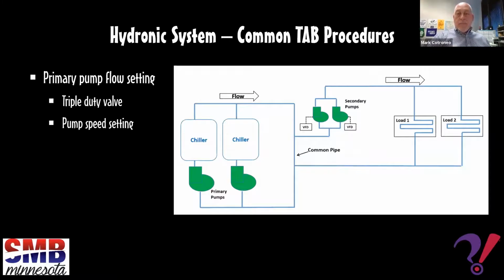For a constant volume primary pump, we would verify that all control valves are open first and foremost. Then we would verify that the gauges are installed in the correct location to gain a measurement, which is directly at the inlet and the outlet of the pump. If they are in the correct locations, the discharge valve will be slowly closed and the gauge read to establish the shutoff head. This process verifies the size of the installed impeller. Starting with the shutoff head that was measured, a new pump flow curve is drawn. Then the discharge valve is opened, the inlet and discharge gauges are read, and the difference in their values is plotted to intersect on the new pump curve. If the flow is too high, the triple duty valve or balancing valve is closed to create pressure and bring the pump to design flow.